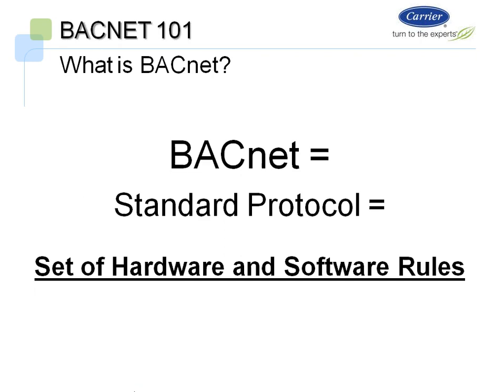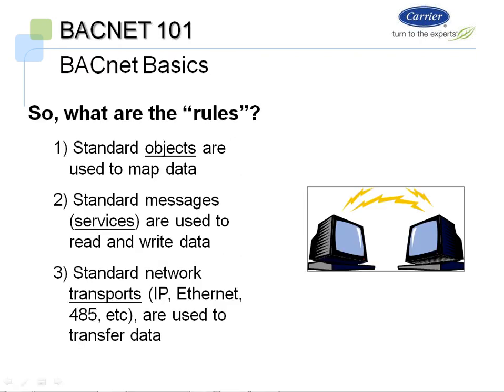So, the set of hardware and software rules for BACnet: the first rule is that any type of information to be shared within the BACnet system is represented by an object, which we'll discuss specifically on the next slide. The second rule is that the way to communicate between objects is with standard messaging or servicing rules, which we'll also discuss. The third rule is that you need a standard network or cable communication bus in order to communicate between these systems.